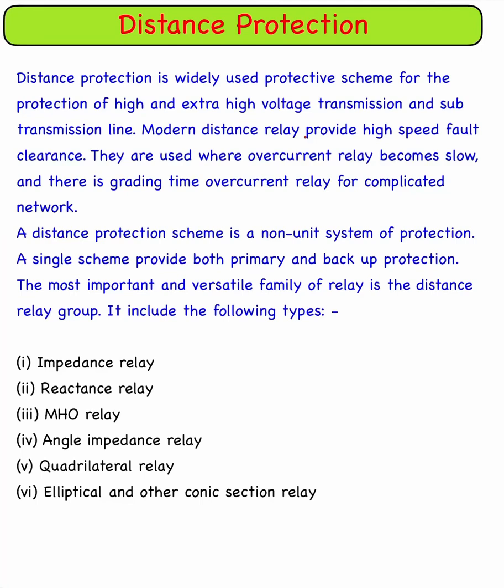Welcome to Basic Electrical. Today we will learn about distance protection and the operating principle of the impedance relay. Distance protection is widely used as a protective scheme for high and extra high voltage transmission and sub-transmission lines. Modern distance relays provide high-speed fault clearance, and they are used where over-current relays become slow due to grading time in complicated networks.